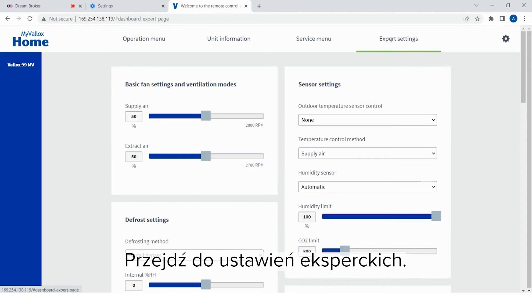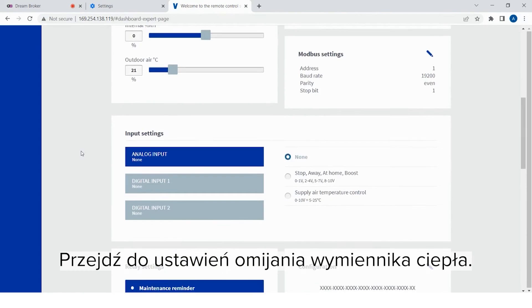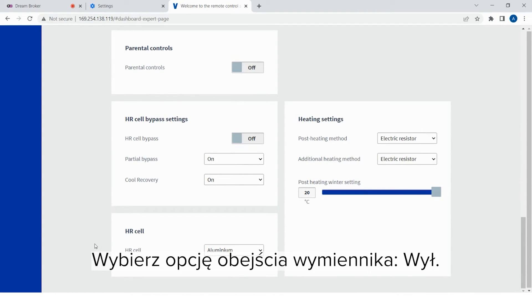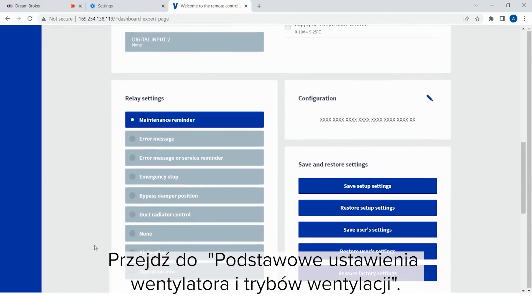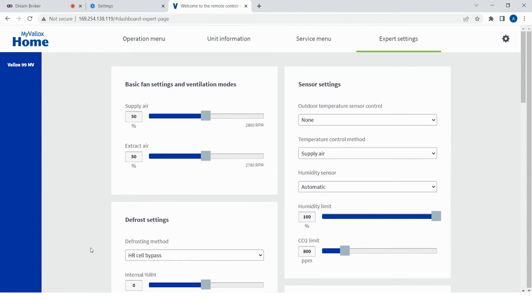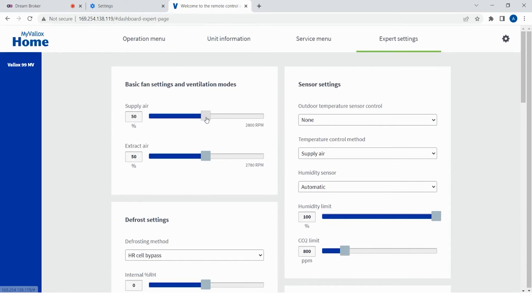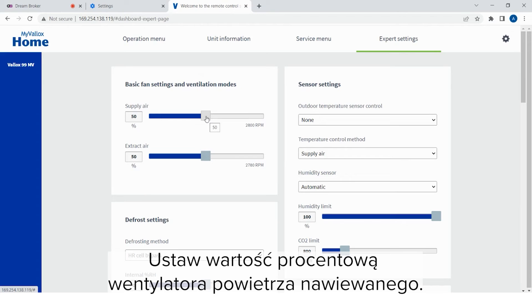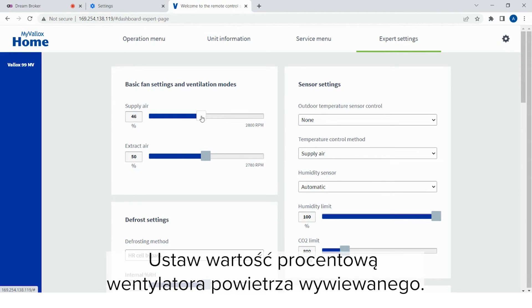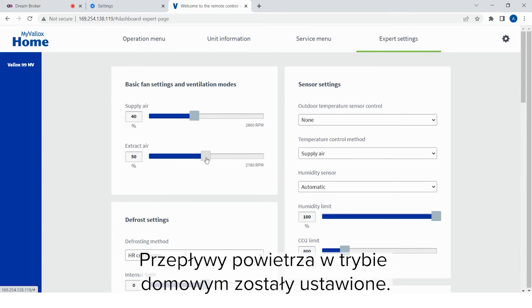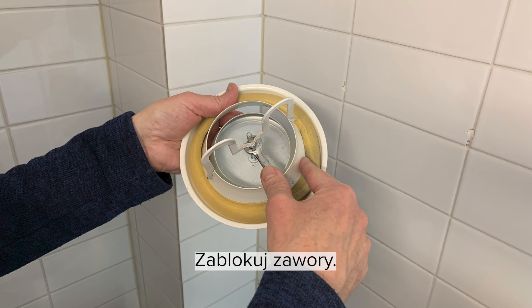Go to expert settings. Go to the bypass settings of the heat recovery cell. Select heat recovery cell bypass off. Go to the basic fan settings and ventilation modes. Adjust the supply and extract air flows of the at-home mode. Measure the air flows from the supply and extract air valves. Set the percentage of the supply air fan. Set the percentage of the extract air fan. The air flows of the at-home mode have now been adjusted. Lock the valves.